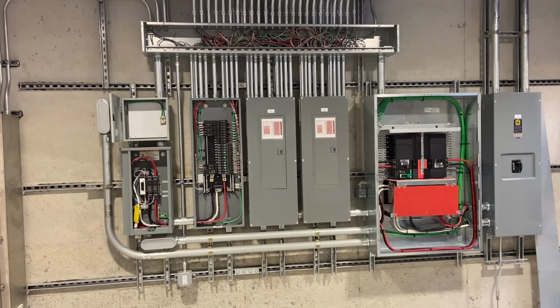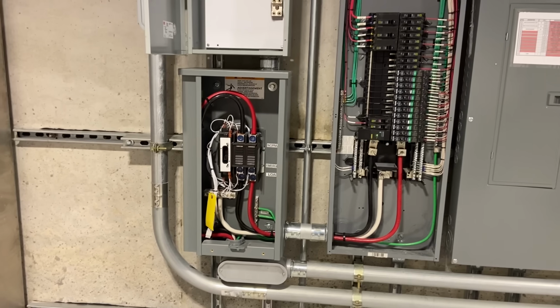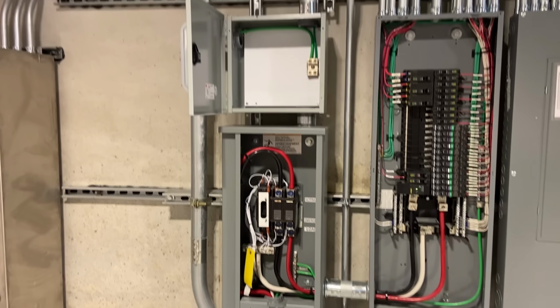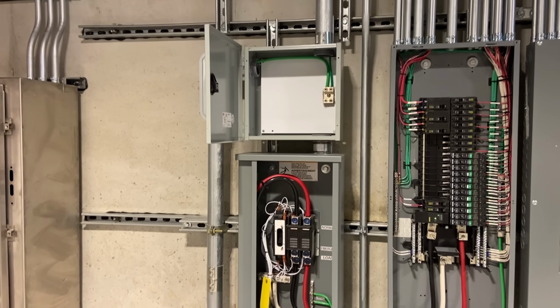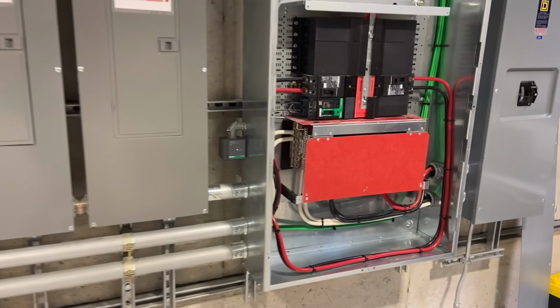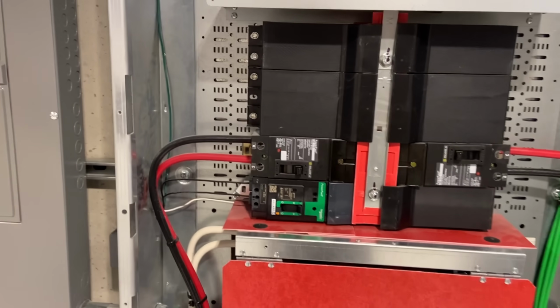Ah, that's better. Here is our essential panel already wired to our ATS. That's a 200 amp ATS Kohler. And our little distribution box, like I said, for the back feed to the main panel. Pipe is already run. I did not run the wires for that, except for the ground.